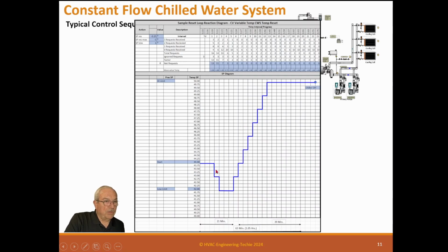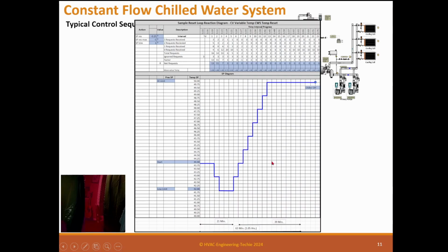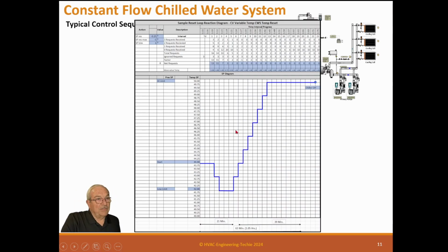And remember that normally this would just bump around 1 degree at a time, or a quarter of a degree at a time, as it goes up and goes down as it needs to. But these are the maximum loops. You don't want to get these too long. If it takes an hour to get where you're going, it could be a problem. So this is just a test, and this is how it will work.